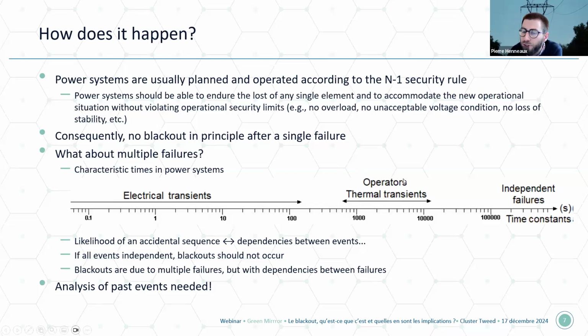Competing also with thermal transients, you have the manual action of operators. If you think of an operator in a control room, if something happens, the operator first needs to understand what's going on, then to think about or compute what the relevant actions could be, and then to implement them. So it will not be faster than a few minutes. It could typically take a few tens of minutes.